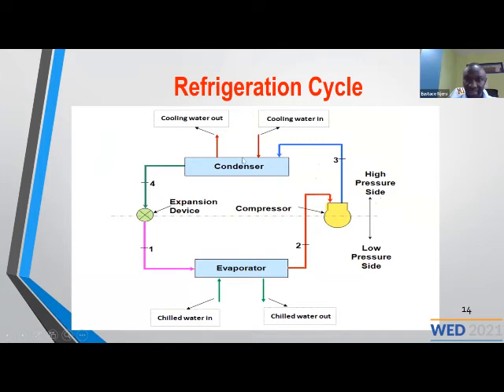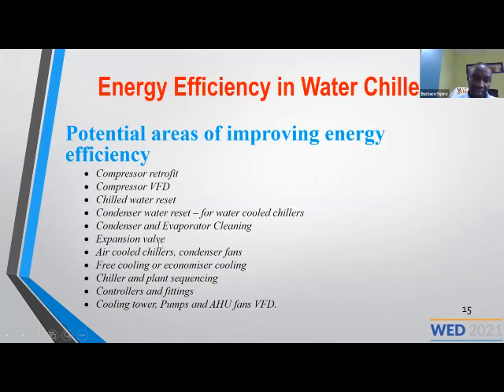So you need very clean. So you need to be monitoring the cleanliness of the evaporators and the condensers so that you can know at what time to stop your water chiller and do the maintenance and cleaning. The other one is expansion valves. Mainly we have what we call thermal expansion valve and electronic expansion valve.